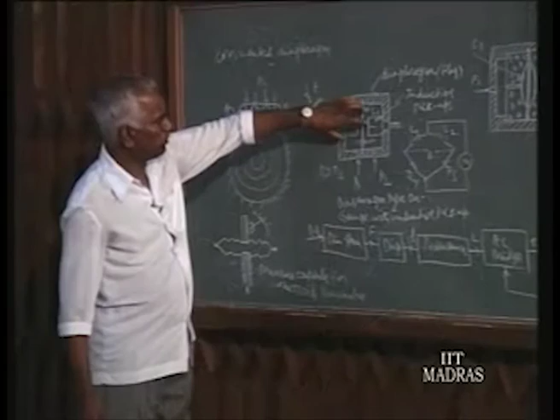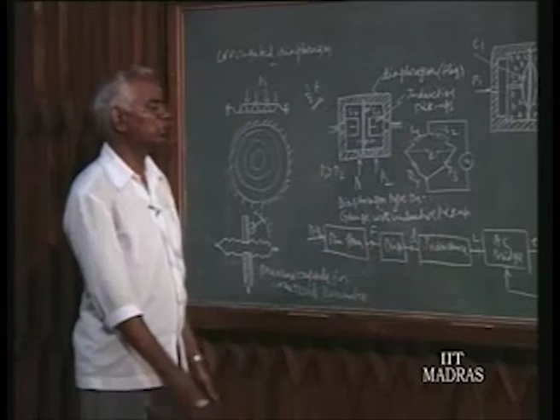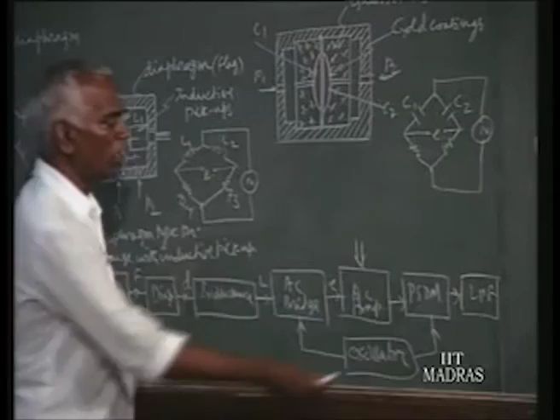The full instrumentation diagram I have given here, and how the basic transducer forms part of the full instrumentation is shown in this signal flow diagram. P1 minus P2, times the area of the diaphragm, will be the force F on the diaphragm. That force acts on the diaphragm and makes a deformation D. That deformation changes the inductance of the coil, and that goes into the AC bridge. The AC bridge gives some output E. This is more or less the output signal.